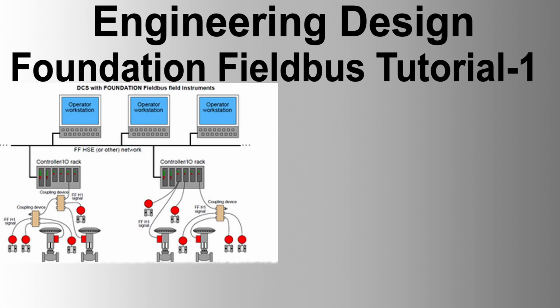Addresses. Communication partners in the data link layer are identified with DL address, which consists of 3 components: link, node, and selector. The link field consists of 16 bits and identifies a link. This field is necessary when a message is going to other links through bridges. The node field gives the node address of 8 bits. A foundation device has a node address in the ranges between 0x10 and 0xFF, which is classified into LM range, basic range, default range, and temporary range. The selector field gives a device internal address of 8 bits to identify a VCR.